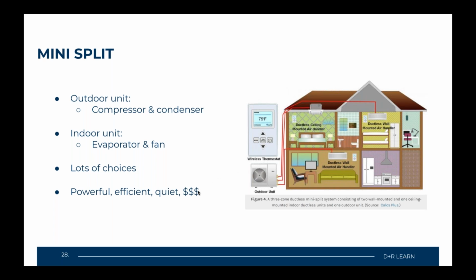Let me come back to that question on the multi-zone systems. On the single zone, you can have that ducted and it's just one temperature, but on multiple systems, I believe they work the same way. Don't quote me on that, but there's a variant. With VRF systems, you can change each zone and room utilizing only one outdoor unit. With mini splits, I believe you have to do something different to operate off one thermostat while changing the temperature in different rooms. I don't have experience on that side. But for the most part, your single zone, especially if ducted, will run the same temperature at every zone or room you're heating or cooling.